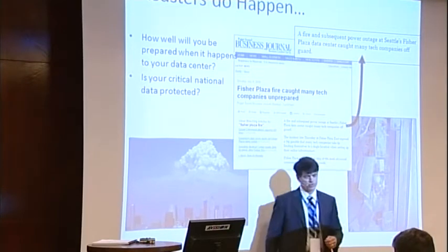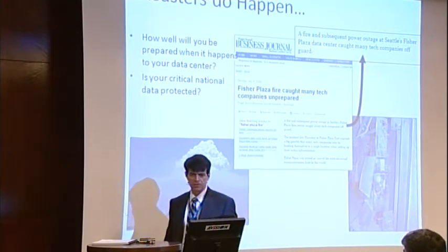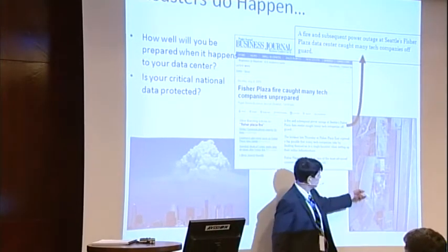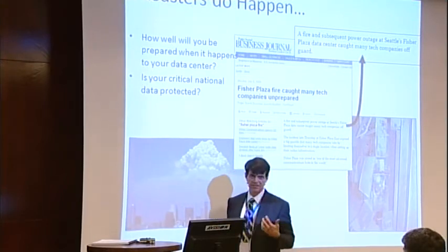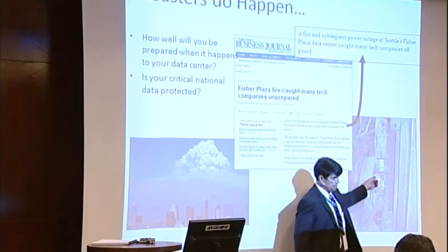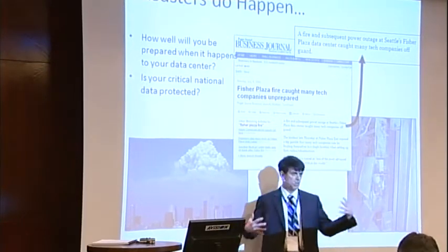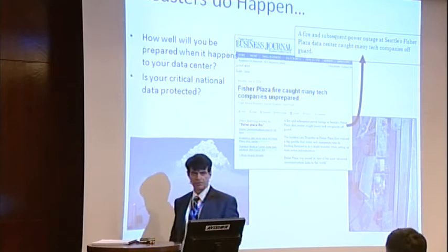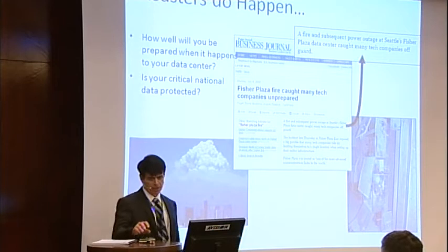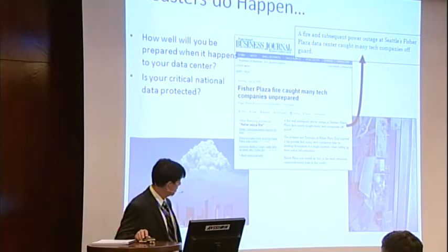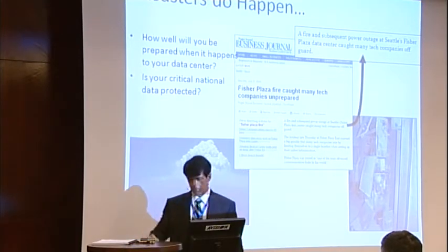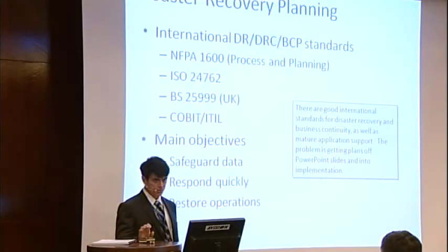This picture that shows a fairly well damaged, disintegrated bus duct is in my own facility, One Wilshire in Los Angeles, which many people believe is the most densely interconnected telecom facility in the world. We had a 4,000 amp bus duct explode right next to the meet-me room where more than 400 carriers interconnect. Disasters do happen, you have to plan for it. Fortunately, our backup systems all operated and the world never knew it happened, but in a disaster like either one of these, global communications could have been set back quite a few years.